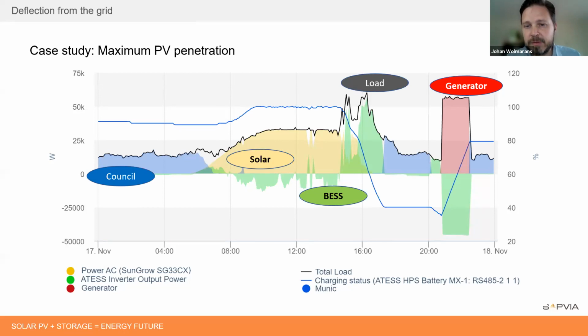And in the afternoon, and this is the case of 17 November, so it's a week or two ago, we had some thunderstorms in the afternoon. You can see now all of a sudden there's no PV available, so we start pushing that energy out of the energy storage system. So typically there are 2 limits that we then apply. The first is the soft limit, where we stop discharging the battery and keep a small reserve. So at around 7 o'clock, the discharge stopped, but at 8 o'clock, load shedding started.